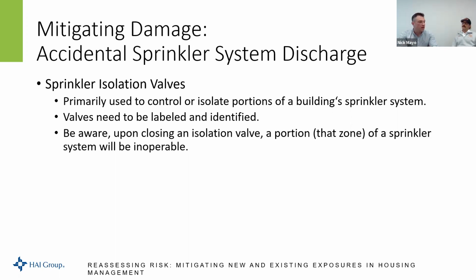But if on floor 4 we had a broken sprinkler head, and then now there's a fire on floor 4, the isolation valve is closed, and therefore water wouldn't come out of that sprinkler head. So it's extremely important to make sure that your fire department knows if any part of your sprinkler system is touched or closed. We need to be aware of that, and you have that relationship.